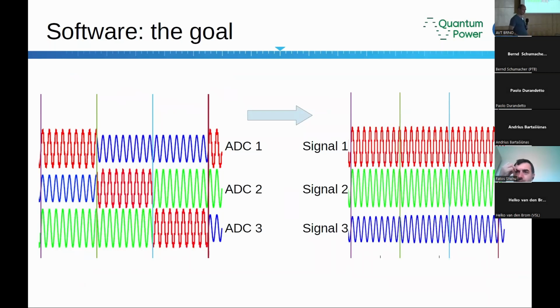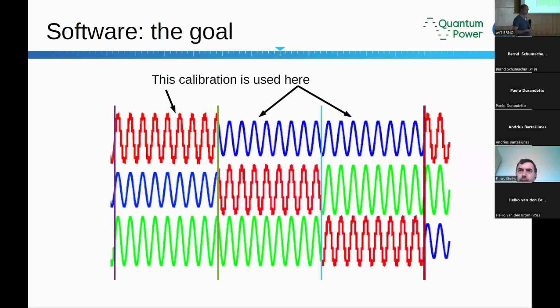So in effect, what the new algorithm has to do is, for example, if we have 3 digitizers measuring Josephson or current or voltage, and the multiplexer is switching the signals between the digitizers, the new algorithm has to order all the signals into the proper parts, so we know what is what and can use the data. As I said, when the digitizer measures the Josephson signal, we use this Josephson signal to calibrate the digitizer, and then we use this calibration for the signal that was measured by the same digitizer later.